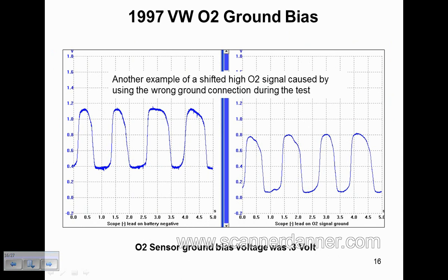So I'm looking at this O2 signal, and I really don't like it. I'm reading 400 to 1100 millivolts — it looks like it's shifted high to me. And I checked my sensor ground, and I read about 300 millivolts on the O2 ground, when what I wanted to see was less than 100 millivolts, because that's a typical sensor ground.